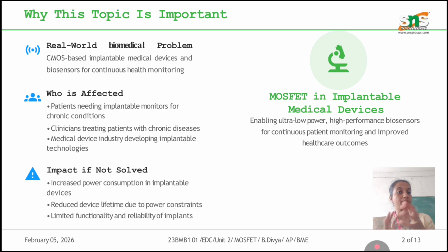What are the impacts we are going to get? Increased power consumption in implantable devices. Once this implantable device is not properly designed or properly incorporated into the patient's body, the power consumption may increase. Since the power consumption increases, the device lifetime will also be reduced.